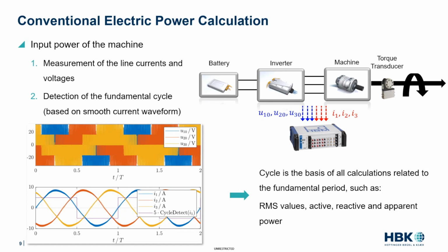And this is the basis for all cycle-based calculations. So not only active power, but also apparent power, reactive power, the calculation of RMS values, but also of efficiency and power factor, for example, or fundamental waveforms. All those quantities are calculated based on this fundamental cycle. So it's very important to have robust fundamental cycle detection in the first step.